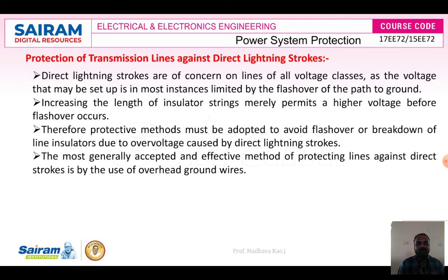Next, the most important consideration is flashovers. To avoid flashovers, we use a path to ground, as the voltage that may be set up is limited by the flashover of the path to ground. And next, we have to increase the strength of the insulation by increasing the number of insulator strings. Increasing the length of insulator strings merely permits a higher voltage before flashover occurs, so you can permit high voltages without damage. So, to avoid flashover or breakdown of line insulators due to overvoltage caused by direct lightning strokes, these are the two methods we can use to avoid flashover or breakdown in the power system.